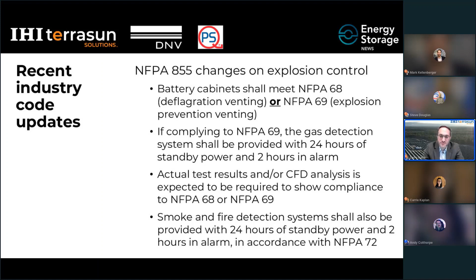At TerraSun, we have previously worked with DNV on projects for NFPA 69 compliance, where very detailed CFD analysis of the full battery cabinet, how gas is removed from the system, and how gas enters the system in a failed state is done to prove that the gas removal will keep the system safe and below the flammability and explosive limits allowed by the code. A final update to note is that with the 2023 edition of NFPA 855, smoke and fire detection systems also have to have similar 24-hour standby power and 2 hours in alarm, and they need to be in accordance with NFPA 72.